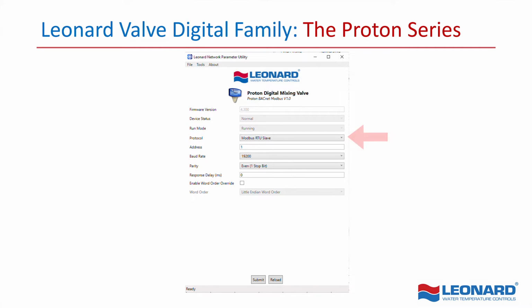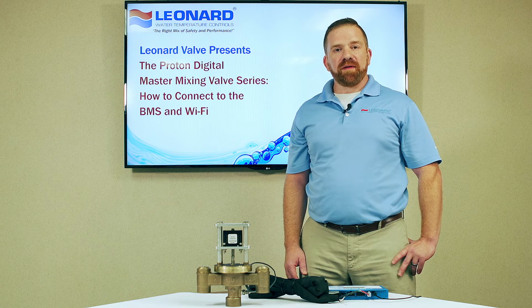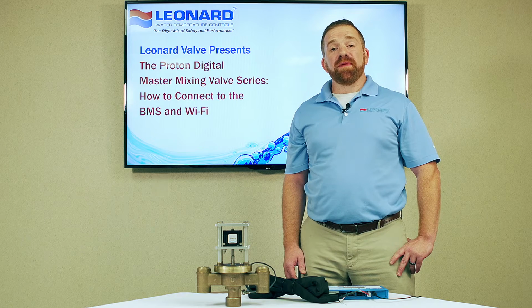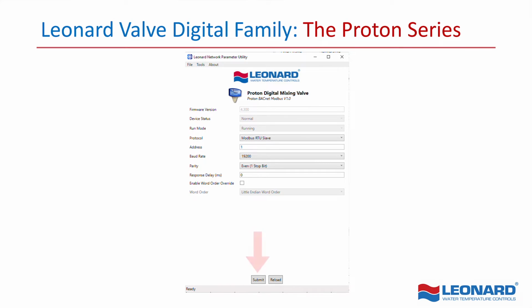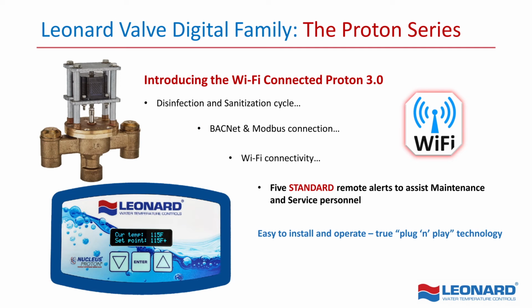This tool allows you to change all the necessary settings for both protocols so that you can integrate it with your BMS. Once all the parameters are set, then you want to go ahead and click the Submit button. This will lock in all the values that you've just entered. And no matter power loss or power failure to the device, these settings will always remain programmed on there. If you have a Wi-Fi setup, you're going to want to have the Proton 3.0 box. This box is capable of BACnet and Modbus just like the 2.5, but with the added capability of Wi-Fi connection.